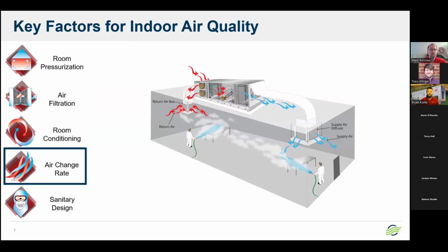So with our units, we have process mode and sanitation mode to align with those process shifts and sanitation shifts. Half an hour or an hour before sanitation comes in, you will switch our unit to cleanup mode, and our unit will go from commonly a mixed air unit, which is taking 5 or 10% outside air mixed with 90 to 95% return air to filter, cool, and heat that air back to the room, to 100% outside makeup air during sanitation. So, for example, if this is a 50,000 CFM unit, 50,000 CFM is coming in from outside air, 50,000 CFM is being pumped into the room, and then 50,000 CFM is being evacuated out of that room.